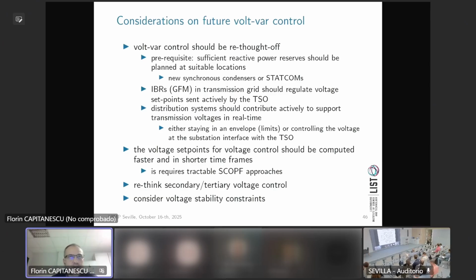So the new generations maybe can be designed, like oversizing the converter a bit in one way or another to have larger capabilities. Especially those that may be at critical locations, like close to a big load center, it's very important to have more reactive power capability by design. But if they are somewhere in the North Sea, very far from any load, at 200 or 300 kilometers from a big load, you may have infinite capability, you can oversize your converter as much as you can, but this reactive power will not serve much, you see. So that was my point.